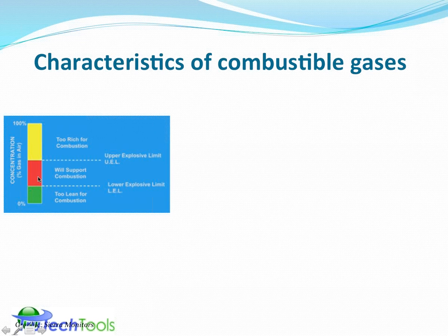It actually moves through a range, this dangerous range, and then above a certain point, there's too much fuel for the oxygen in standard air, which has 20.9% oxygen in it. There's too much fuel for the oxygen that's available, so it cannot support combustion. This is green because it's considered more safe, red because it's dangerous, and yellow because there's a caution.